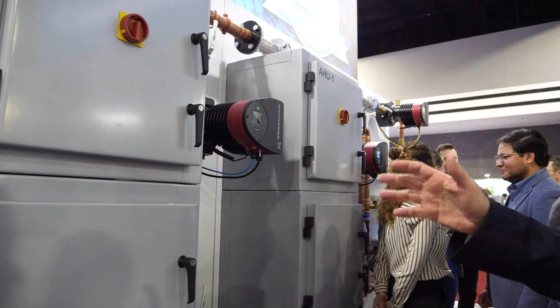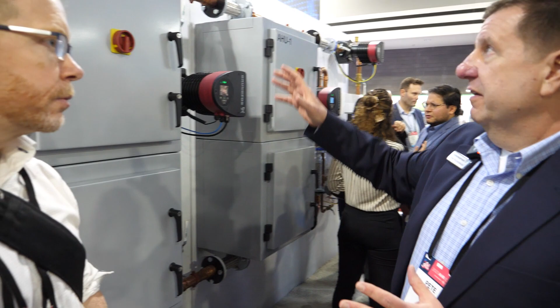So we've got a pump. You can't really see around the corner. There's a check valve because if one of these isn't calling, we don't want flow back through it. So, you know, we'll have that check valve there. But that's really it. So what we'll do essentially is no different than what you would do with the control valve. If you could imagine an air duct here, if we could have had that, we'd have an outgoing air temperature sensor, 4 to 20 or 0 to 10. We'd wire that directly back to the pump. All the inputs and outputs are there for it. And then we'd speed up and slow down to match the demand that we would have at this air handler. This pump will act independently of the next one and independently of everyone down the line.